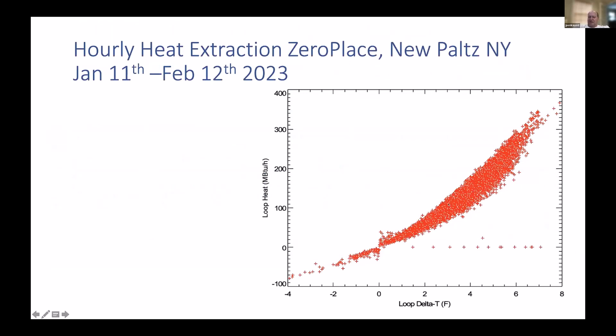This is another way of looking at it, and it just determines how much this was here. It quantitates it. So this is 0 delta T at the loop field. If we're going down here, we actually are operating in cooling mode. And you can nicely see here, this is really between January 11th and February 12th. And you can see how the delta T goes up when there's a more heating need. And we had -6 degrees in New Paltz, where zero place is. And we were pulling out up to about close to 380 MBTUs per hour.